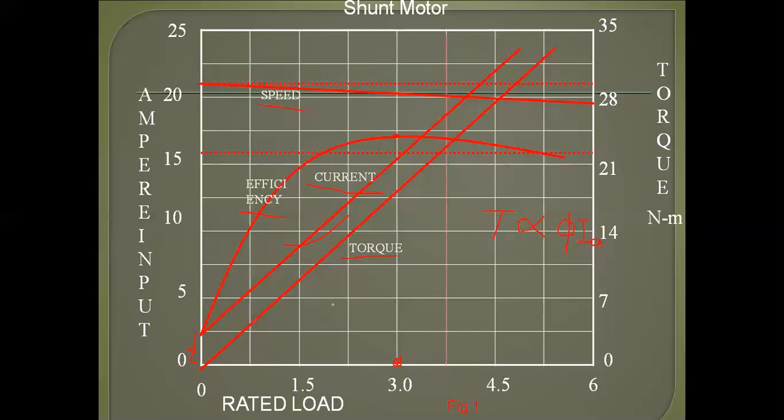A shunt wound motor is said to have a low starting torque as compared to other motors, but it does not mean that a shunt motor is incapable of starting heavy loads. A shunt motor is capable of starting heavy loads also, but it requires more excess of current input over normal values than the series and compound motors.